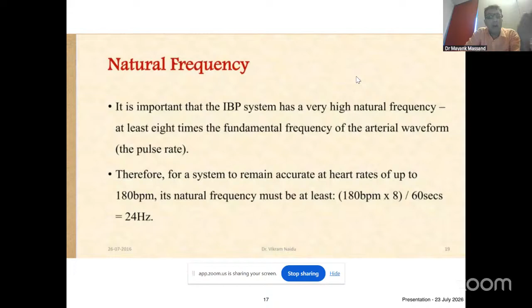At heart rates of up to 180 beats per minute, its natural frequency must be 180 into 8 divided by 60, that is 24 hertz. This 24 hertz is the figure to be remembered for the purpose of arterial blood pressure monitoring, because we take 180 beats per minute as the baseline.